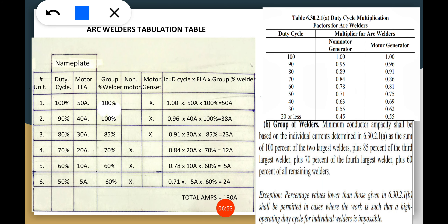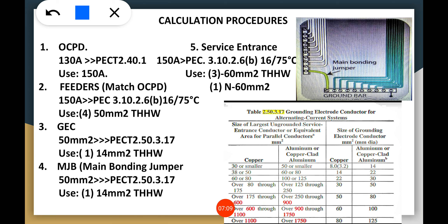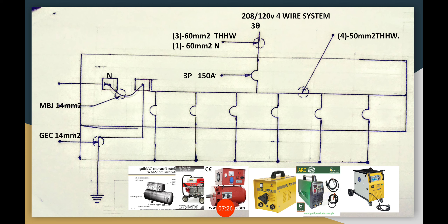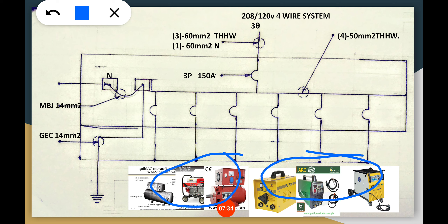For the OCPD, we take the 130-ampere total and go to PEC 240.16. We don't multiply by 200% here — that 200% applies only to individual arc welding machines, not to a group of welders. For the group welder, we simply go to PEC 240.16 and use 150 amperes as the OCPD.